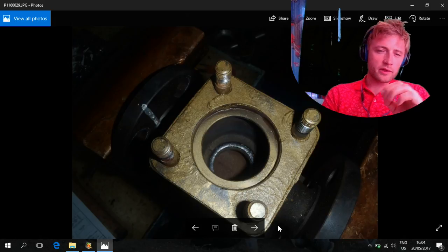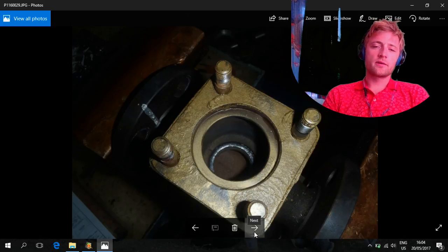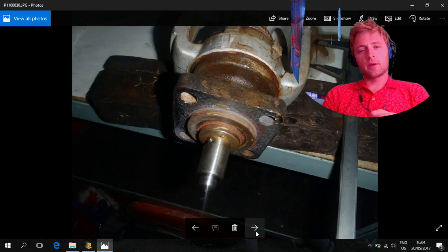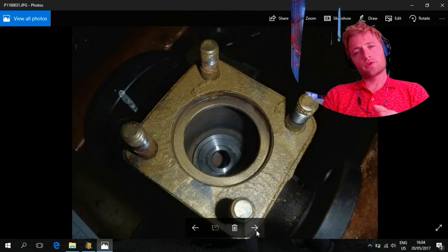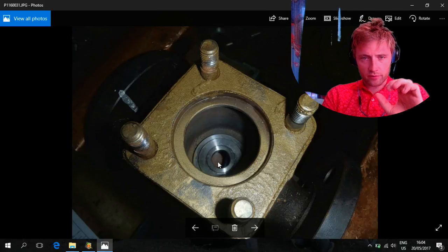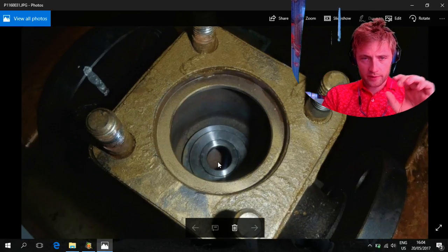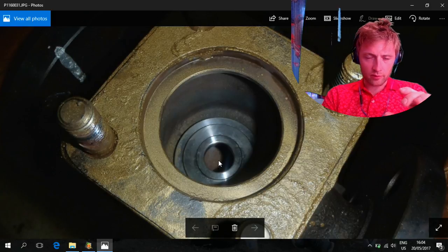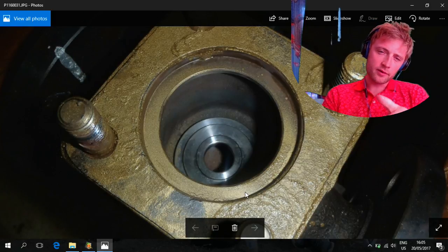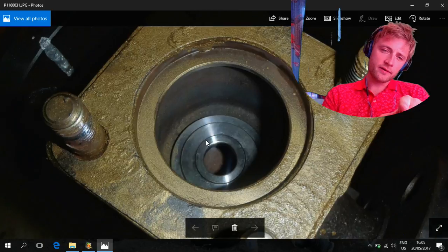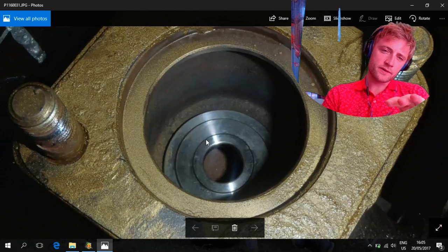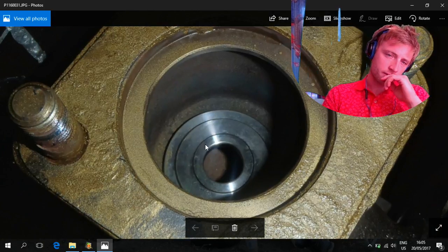This is complete with new shaft, new seat. Check the drawing exactly for how the seat is going, because I found in one valve of the diesel generator the seat was turned the other side.